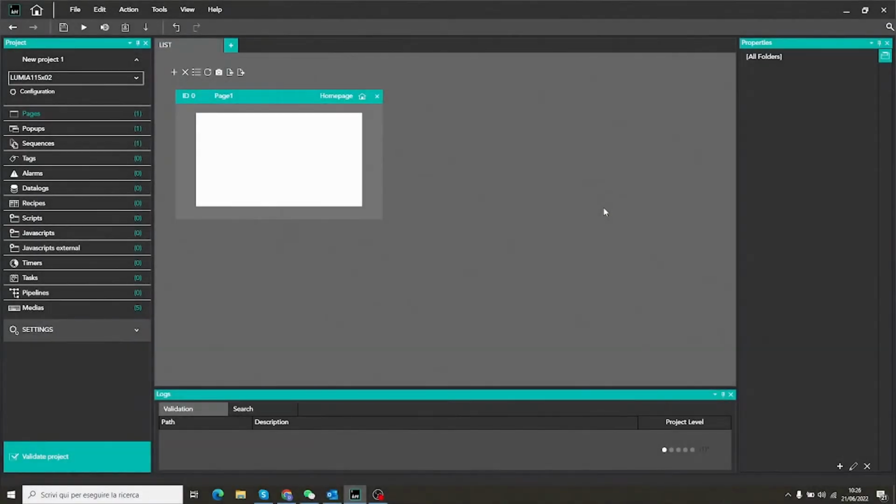Welcome to this tutorial video, which is dedicated to the alarm programming in Creo. So let's start from an empty project. In this project we have page 1 only, so the home page, and we don't have any tag, any alarm, nothing basically. So the first step is define the tag where the alarm will be mapped.